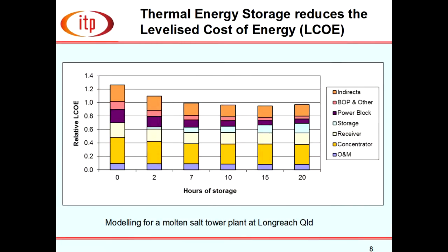If you can take your salt up to 600°C instead of 380°C, you're putting more energy into the same kilogram of salt, the same tanks, and the same heat exchangers — better bang for your buck at higher temperatures. There's also an interesting idea of putting electric heaters in these tanks as a way of storing electricity if you've already built your solar thermal plant.